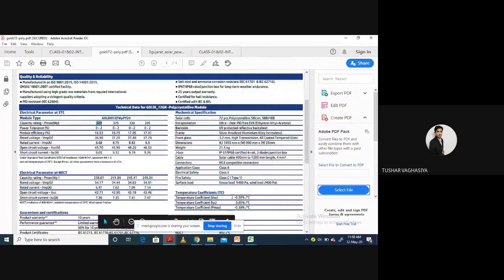Here is the coefficient of VOC. If we increase temperature, what does the coefficient say? If we are increasing the temperature, then VOC will decrease by 0.30%. VOC is 45.70 at 25 degrees Celsius. If temperature rises to 30 degrees Celsius, VOC will decrease 0.30% per degree Celsius.